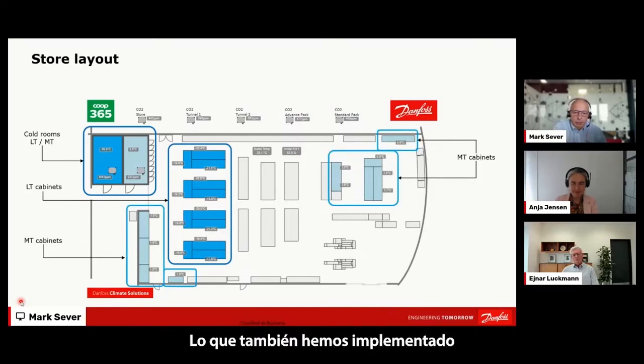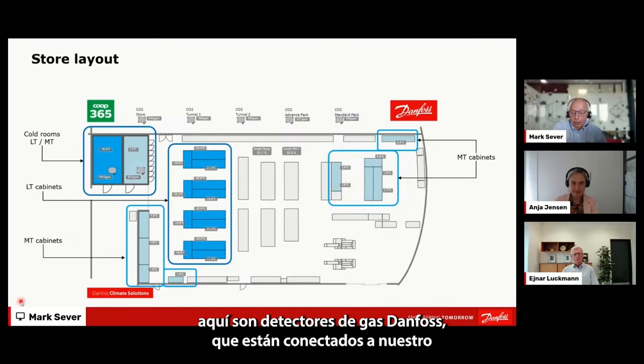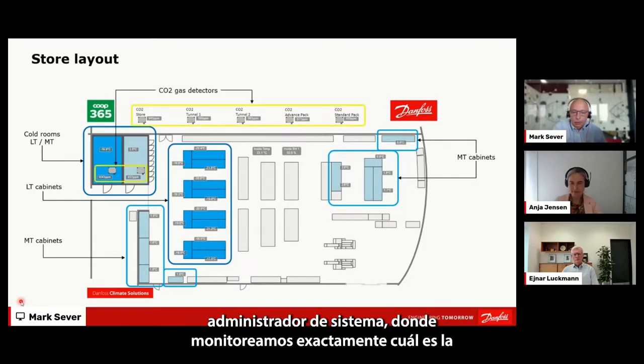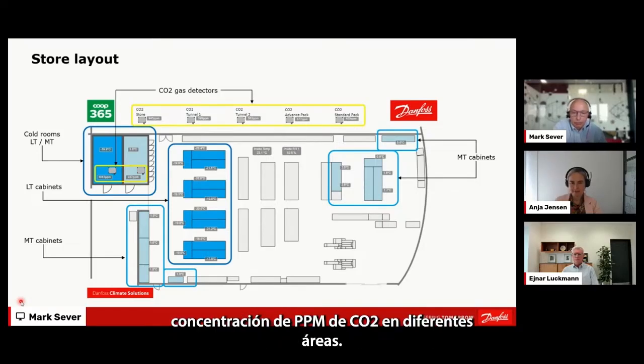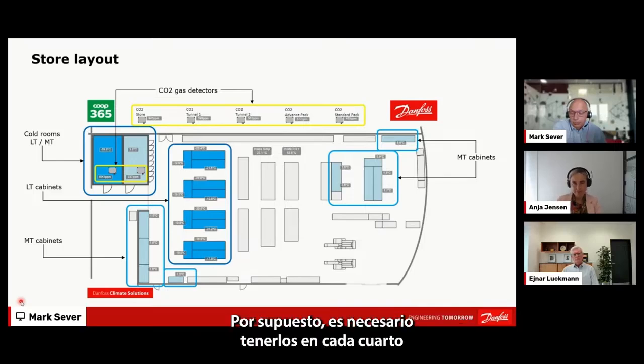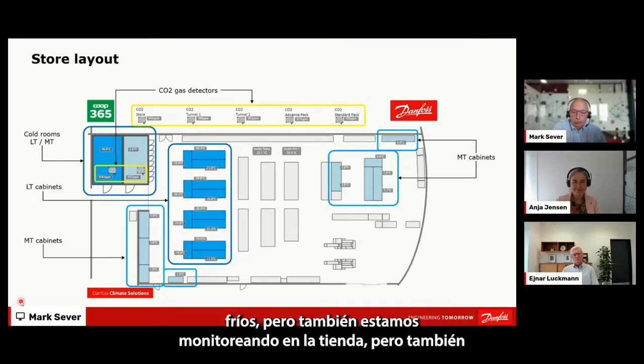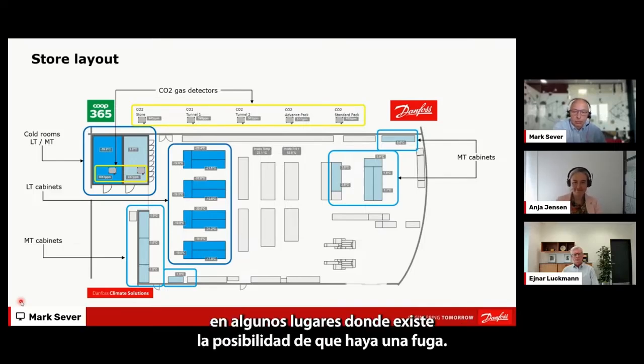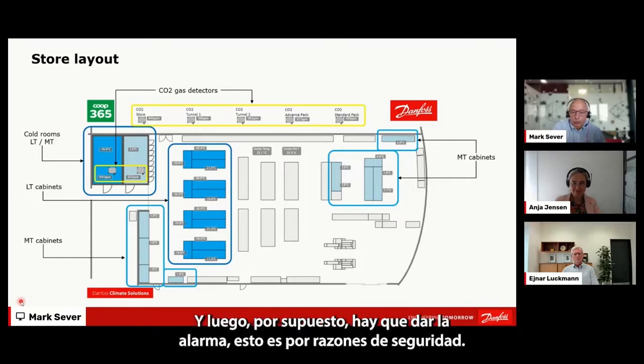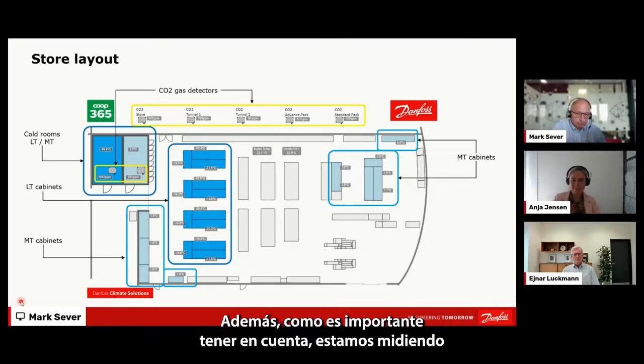What we also have implemented here are Danfoss gas detectors, which are connected to our system manager, where we are monitoring exactly the concentration of ppm CO2 in different areas. Of course you need to have this in each cold room, but also we are monitoring in the store, and in some places where there is a possibility of leakage, and then of course you need to give an alarm. This is for security reasons.